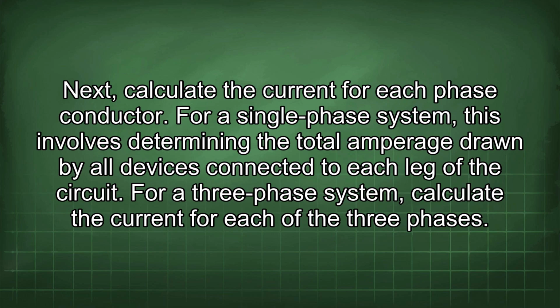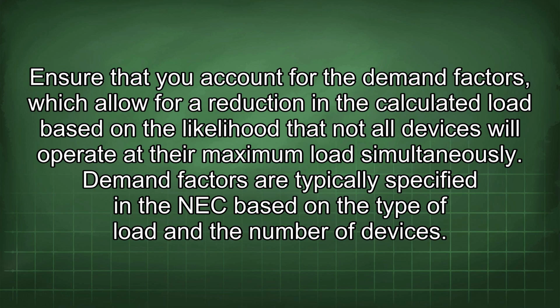Next, calculate the current for each phase conductor. For a single-phase system, this involves determining the total amperage drawn by all devices connected to each leg of the circuit. For a 3-phase system, calculate the current for each of the 3 phases. Ensure that you account for the demand factors, which allow for a reduction in the calculated load based on the likelihood that not all devices will operate at their maximum load simultaneously. Demand factors are typically specified in the NEC based on the type of load and the number of devices.